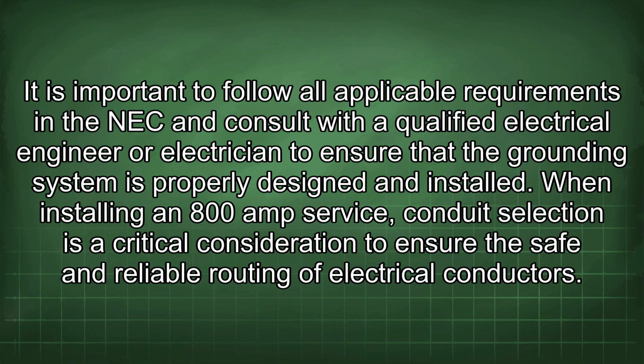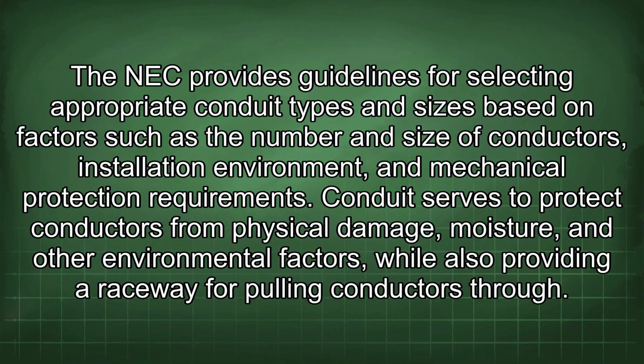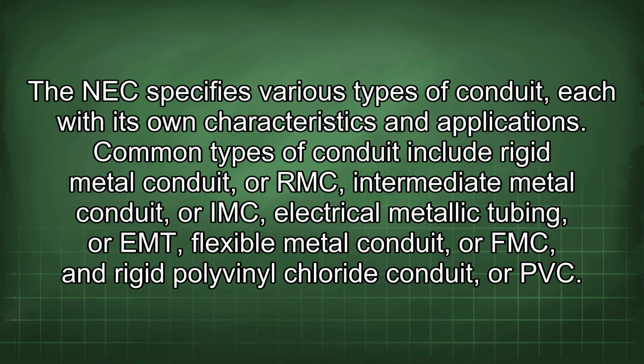When installing an 800 amp service, conduit selection is a critical consideration to ensure the safe and reliable routing of electrical conductors. The NEC provides guidelines for selecting appropriate conduit types and sizes based on factors such as the number and size of conductors, installation environment, and mechanical protection requirements. Conduit serves to protect conductors from physical damage, moisture, and other environmental factors, while also providing a raceway for pulling conductors through. The NEC specifies various types of conduit, each with its own characteristics and applications.